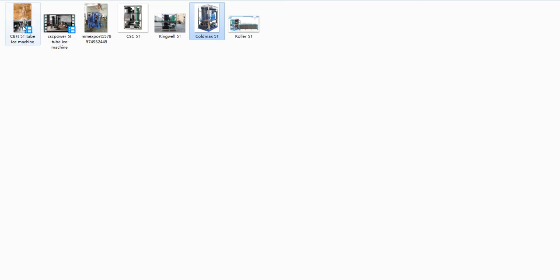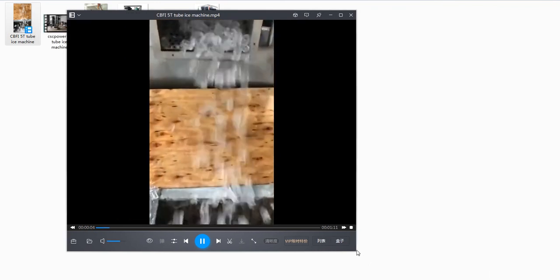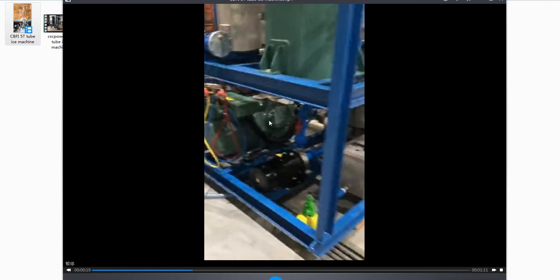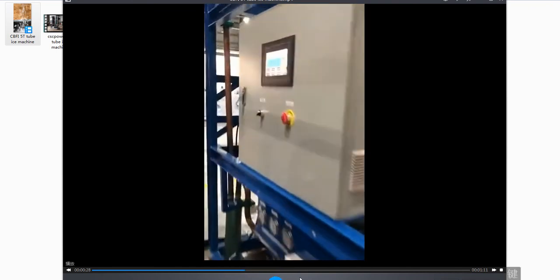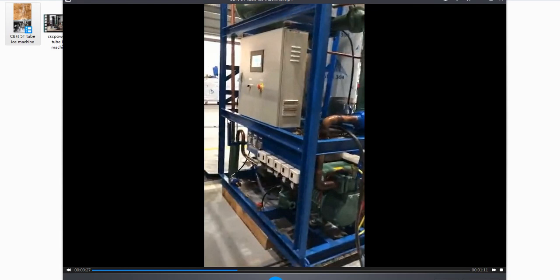This is the CBFI tube ice machine. The ice is not solid — it's milky white, that is not perfect. Here is the 25-horsepower piston compressor with six pistons. This system is not efficient either — it's simple and poor technology. One more thing: the machine frame is made of carbon steel with painting, which is not good for making food-quality ice tubes. We should use stainless steel.